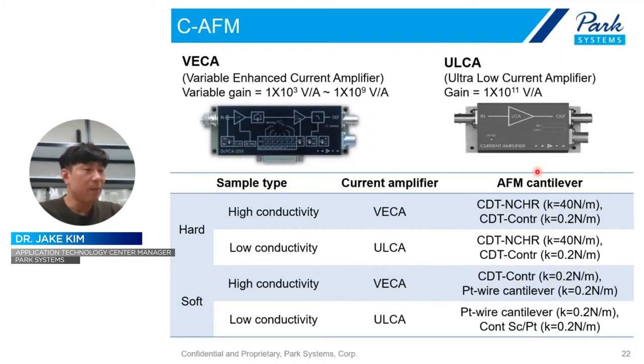The key part of conductive AFM is the current amplifier. There are two types. One is the VCA, the variable enhanced current amplifier, and the other one is the ULCA, the ultra low current amplifier. The difference is the detecting range. Roughly speaking, if your sample has a high conductivity, you should apply the VCA. But if your sample has a low conductivity, for example, less than a few picoampere or less than a picoampere, you have to apply the ULCA. So depending on the signal or the sample type, we can apply each current amplifier.